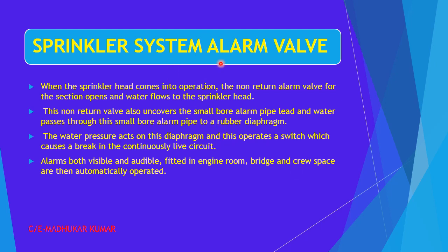What is the system alarm valve? When the sprinkler head comes into operation, the non-return valve for the section opens and the water flows into the sprinkler head. This is the section valve; we are talking about each section. This non-return valve also uncovers the small bore alarm pipe, and the water passes through the little bore alarm pipe to the rubber diaphragm. The water pressure acts on the diaphragm, and this operates a switch which causes a break in a continuously live circuit, and this will give you the alarm. Both audio and visual alarms fitted in the engine room, bridge, and crew spaces are automatically operated. So how the alarm comes has been explained.